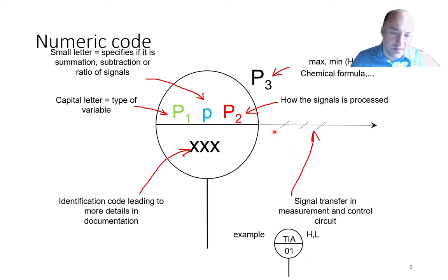And you may have a signal like this. This is telling you this. The signal line, where is it going? You can see that it's a thin line, eventually with an arrow, which tells us the signal direction. And here you have those crosses under 60 degrees. So this tells me that this signal is not the flow of material in my process, but that this is the signal from my sensor and eventually some control signal.